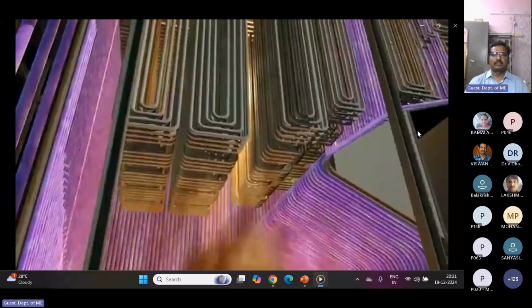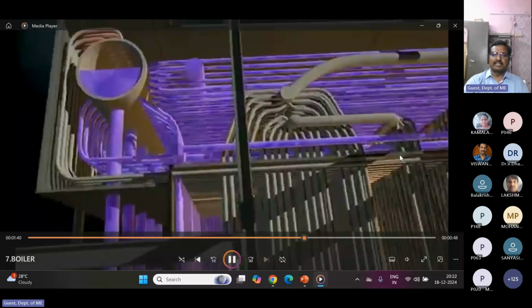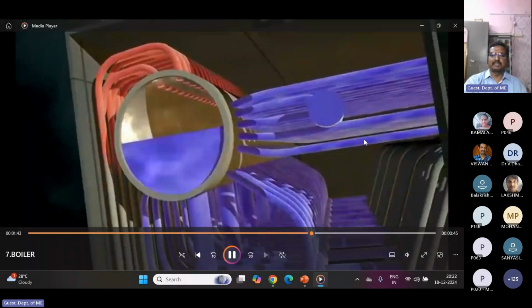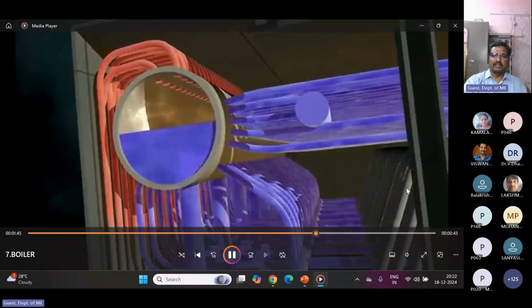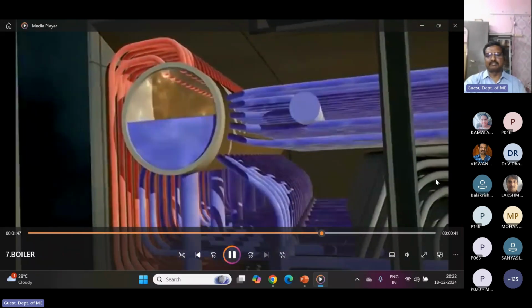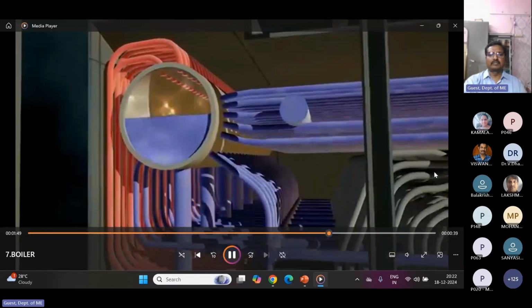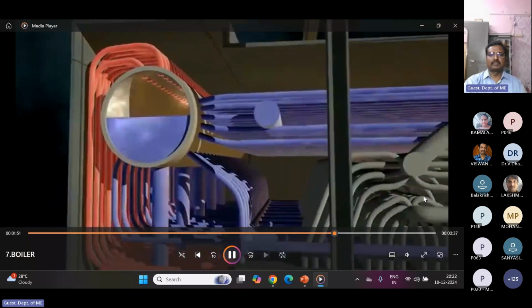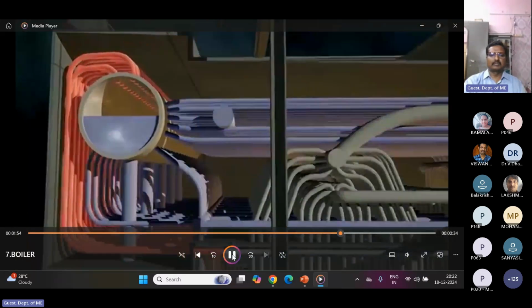At the point in the cycle when the liquid water turns to steam, the steam separates and collects at the top of the steam drum. Because this saturated steam still contains small amounts of liquid water that would cause corrosive damage to the turbine, the saturated steam is routed back into the superheater coil.